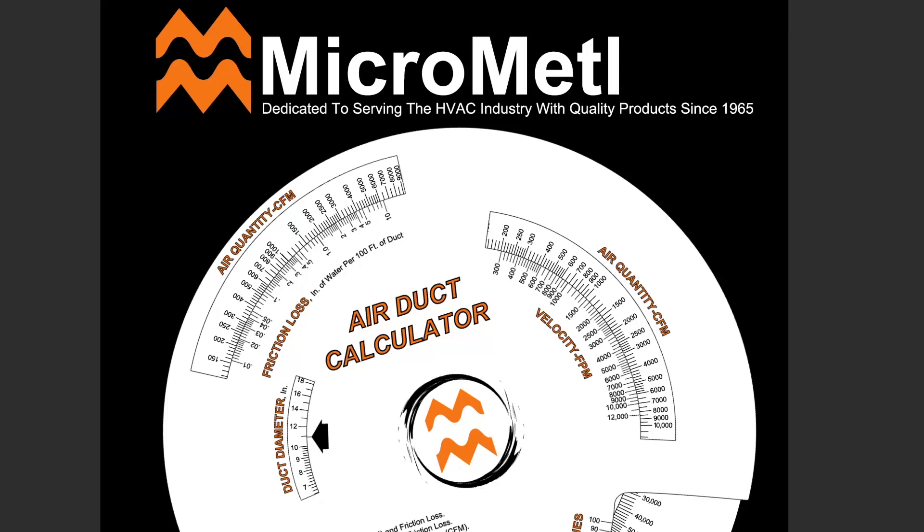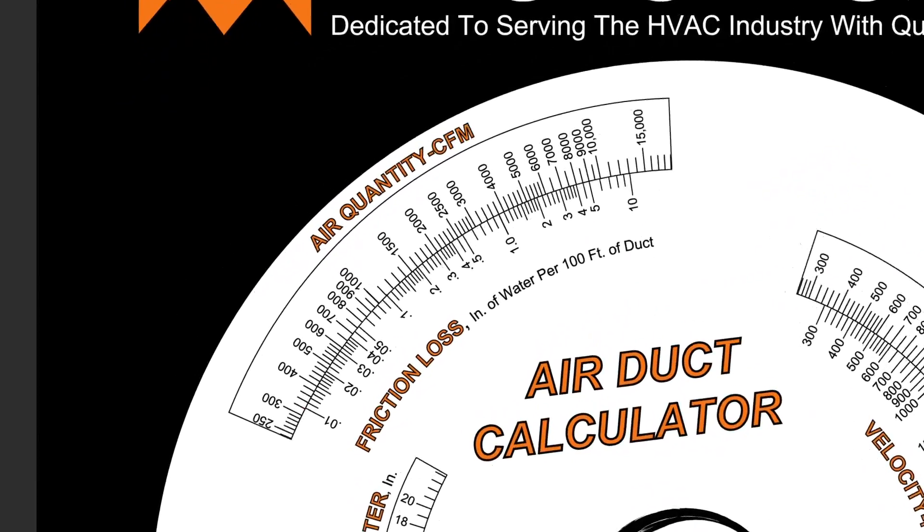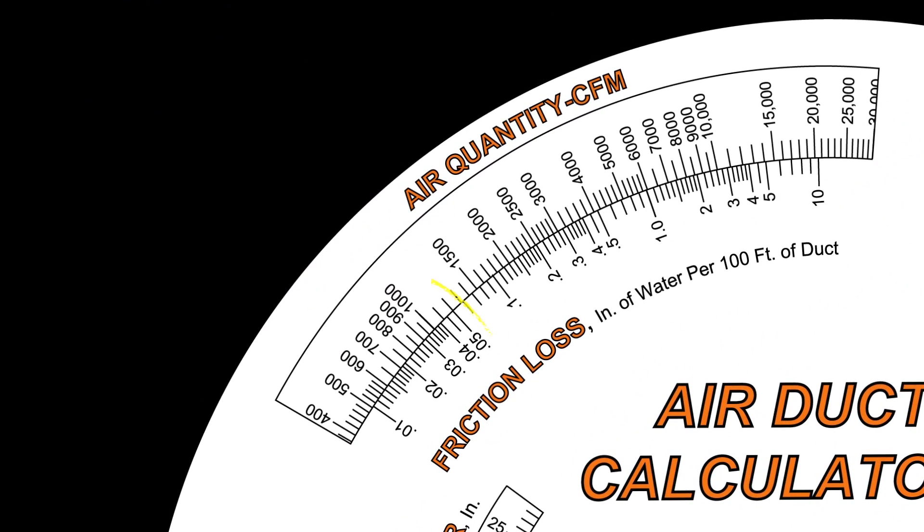Let's use a quick design example. Let's say you have a three ton unit. Each ton of air is equal to 400 CFM according to most standards. Therefore, your three ton RTU is pushing 1200 CFM. Let's assume you want your duct to introduce no more friction than a half inch of static pressure or 0.5 on our friction loss chart. Align the 0.5 at the bottom to an air quantity of 1200 CFM.